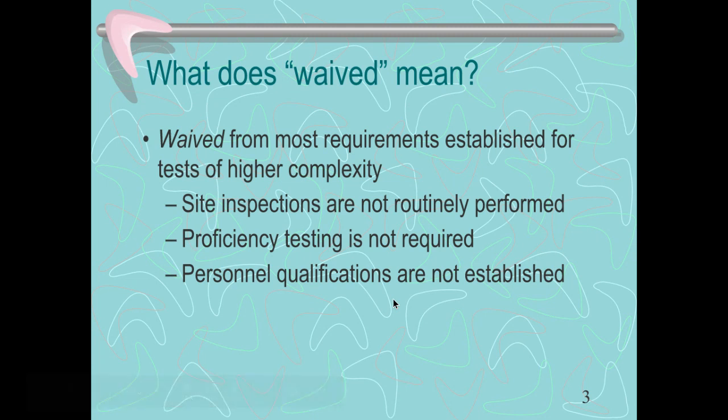Sorry, guys, they're not going to come in every 18 months to inspect your lab. They're going to come in every 3 to 5 years or even longer sometimes. Proficiency testing is not required, so there doesn't need to be a control done every 10 tests.